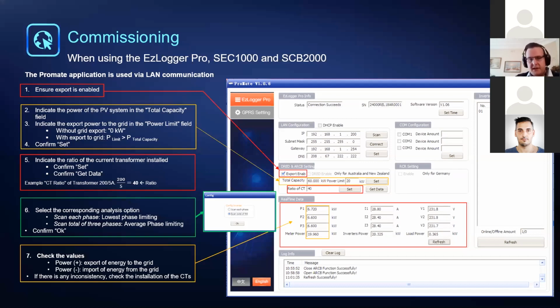After that, we must check our values. So here we'll see the values read by each CT. We want to make sure that they are all reading similar values. Positive will indicate that we are exporting energy to the grid. Negative will mean we are importing energy from the grid. So if we see an imbalance here, when the inverter is not producing power, then we'll know whether our CTs are either incorrectly installed or we have the incorrect line connected.